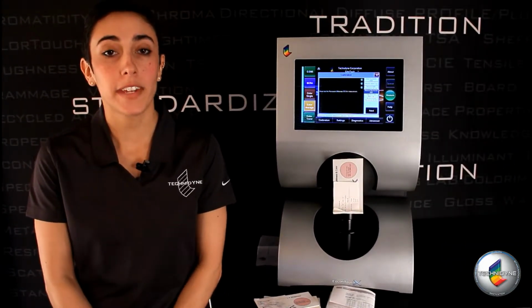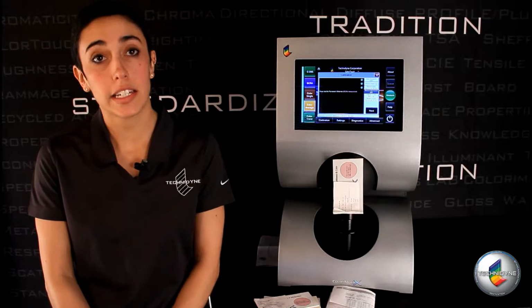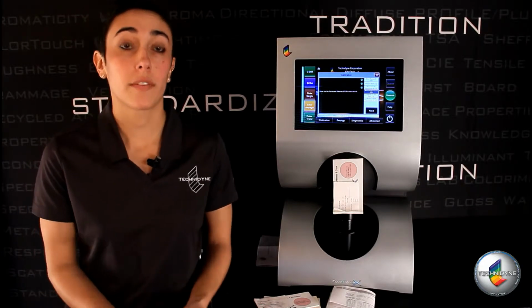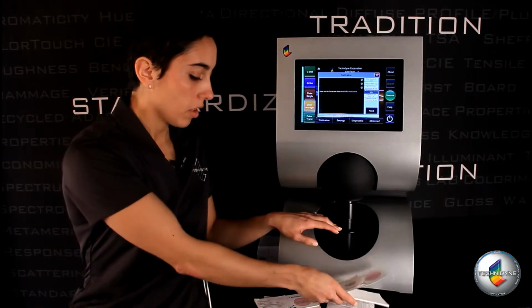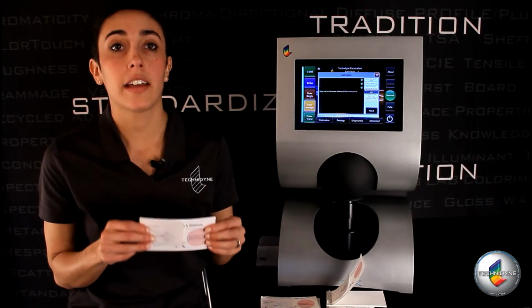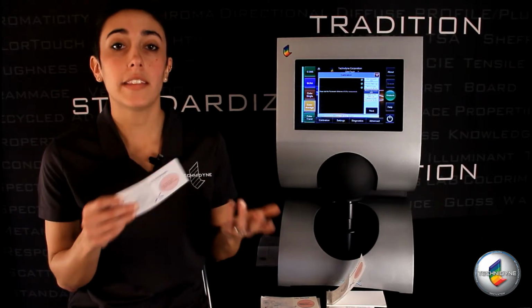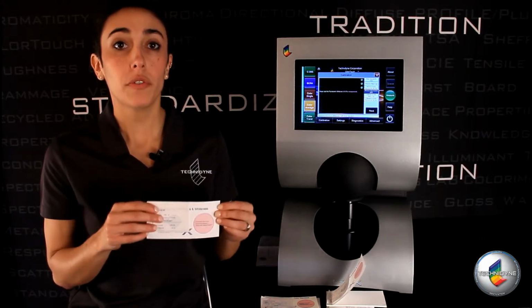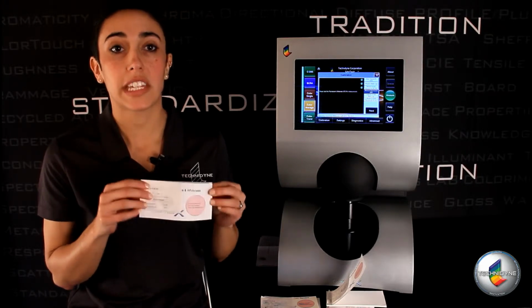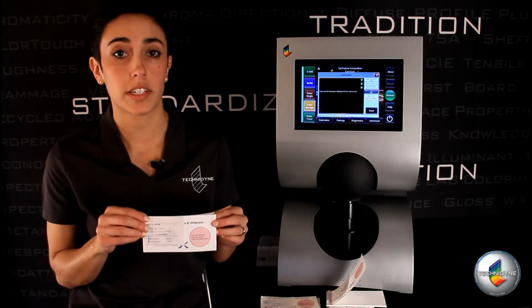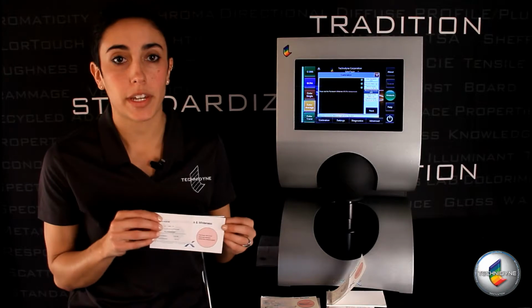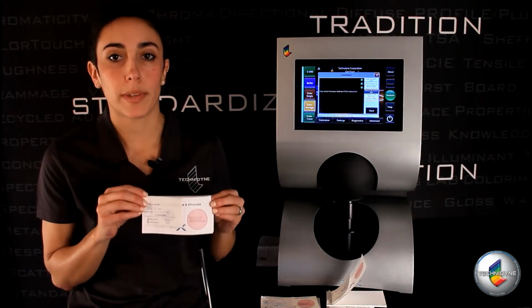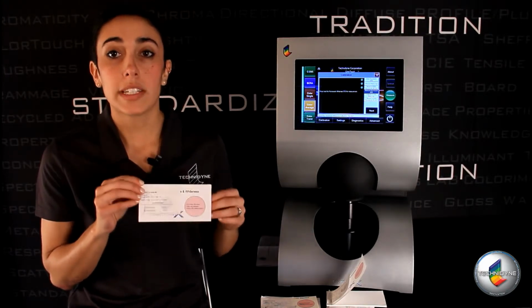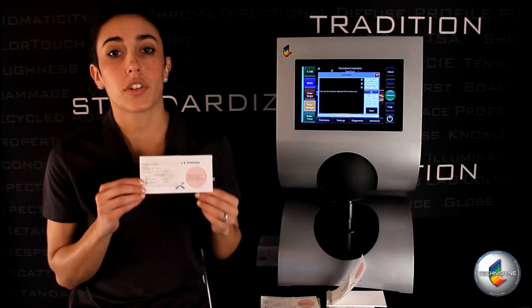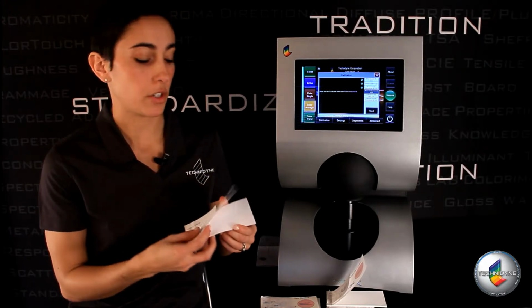Once the instrument is finished measuring the non-fluorescent 90 standard, it will ask you to measure the fluorescent standard. Once again, you'll need to verify the serial number. In this step, the instrument will measure the UV filter positions for both the D65 and the C sources. This process can take a minute or so as multiple measurements are established. Once these values are established, motor positions are saved in the software for future measurements.